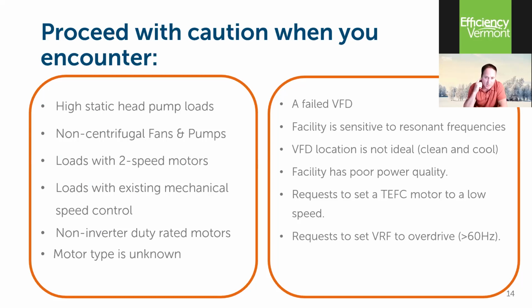Loads with 2-speed motors. I talked about this in the context of the kitchen hood fans. It's not a no-go per se. It's just a moment to pause and maybe ask a couple extra questions. If we're really in doubt, let's log the motor with a power logger and see if we can get some more intelligence on how much energy it's consuming in the baseline condition, and then how much more we could slow it down while still meeting demand with a VFD.